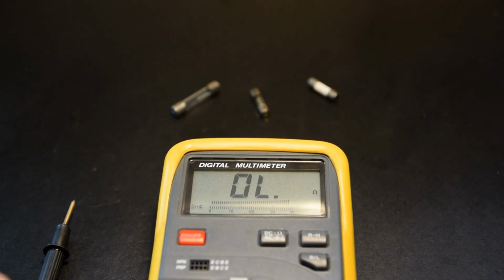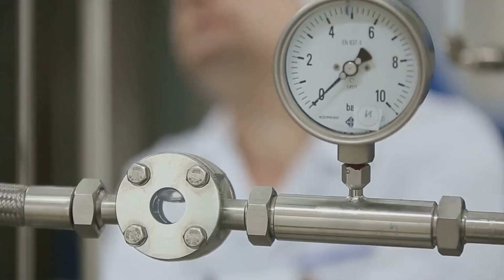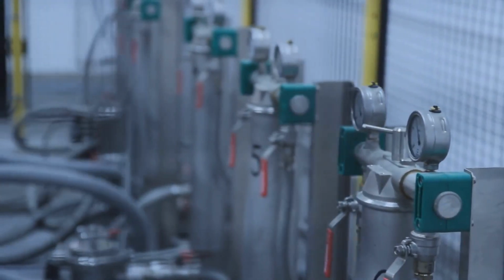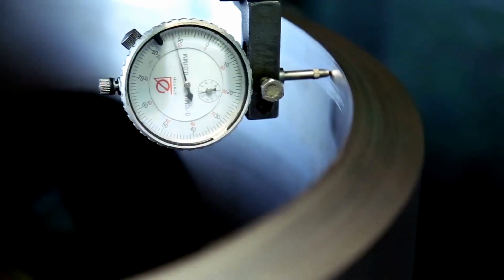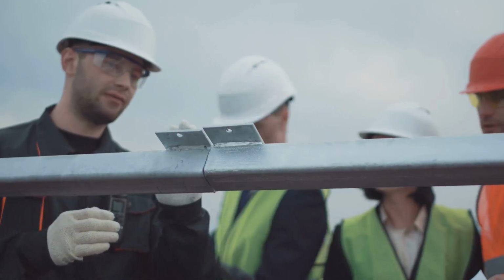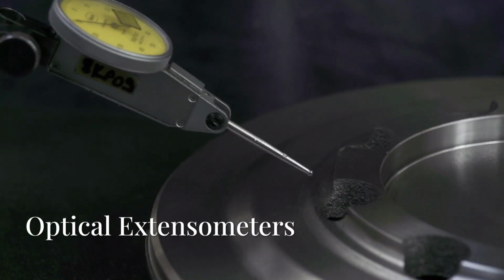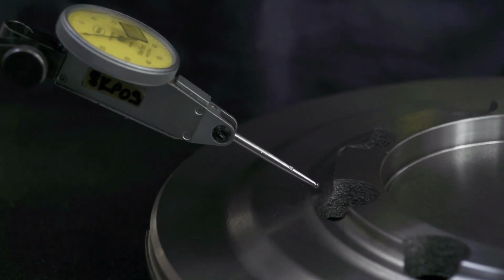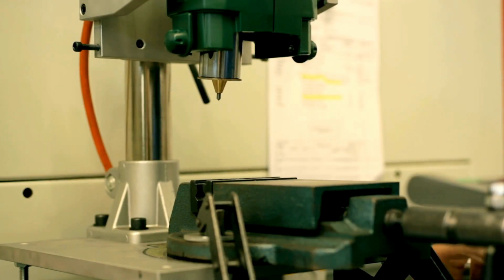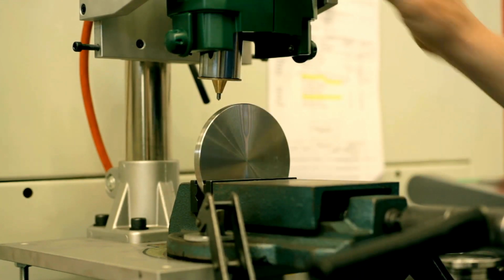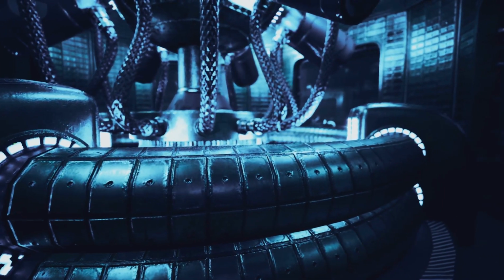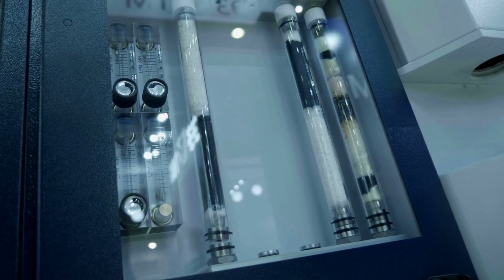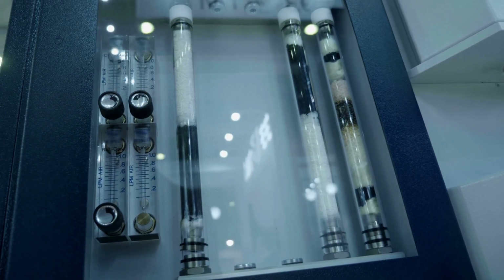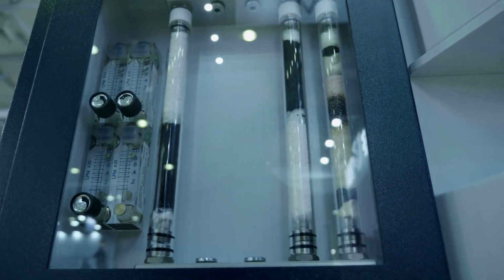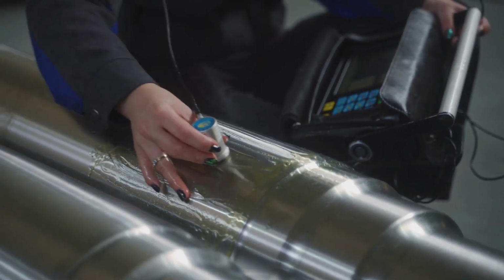So, electrical resistance strain gauges are these thin electrical devices that get bonded to surfaces, and they actually change their resistance as they deform. They're often employed in experimental stress analysis to measure strain in metals, composites, and even concrete structures. Optical extensometers, on the other hand, use laser or optical systems to measure displacement without any physical contact. They rely on light interference patterns or laser triangulation. These are really ideal for non-contact measurements, making them especially useful for high-temperature applications or for sensitive materials where contact could actually affect the results.